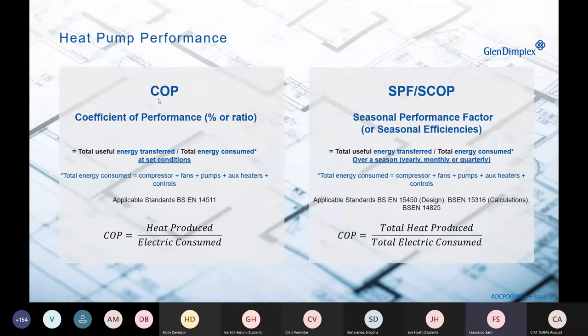The COP is the coefficient of performance and simply measures, following BS EN 14511, this very simple formula. It's tested in the lab, and the heat produced divided by the electricity consumed by the compressor gives you the COP. When you go to the SCOP or SPF, as you can see, the word seasonal is added.